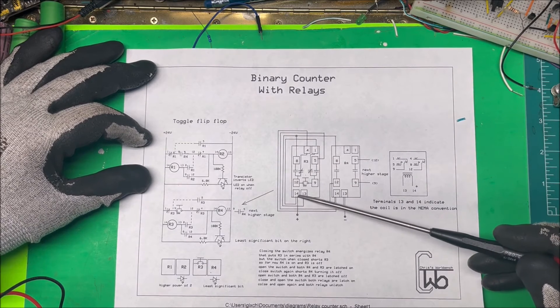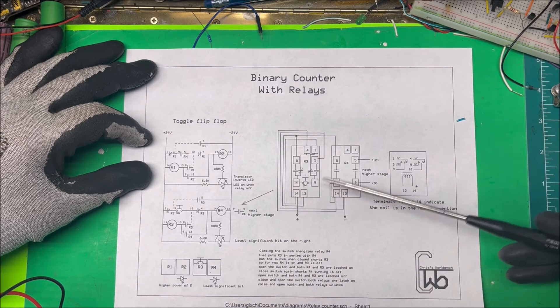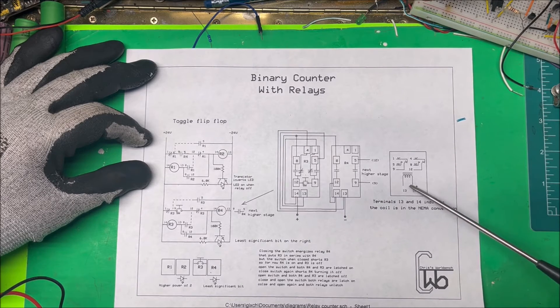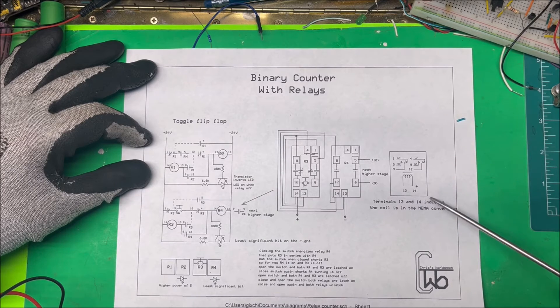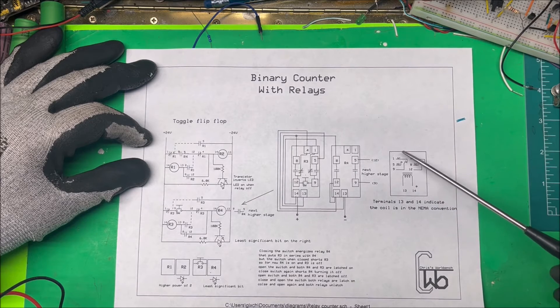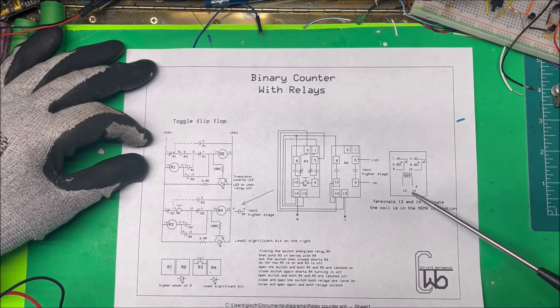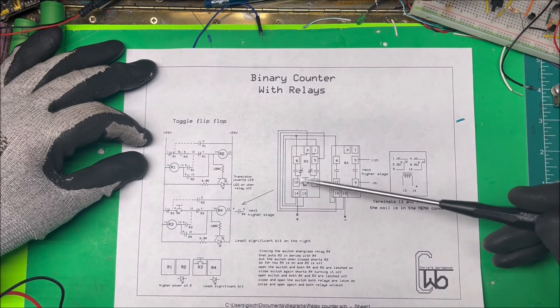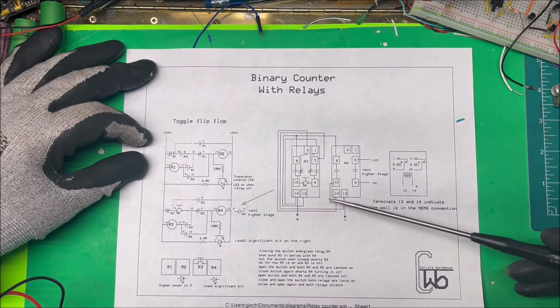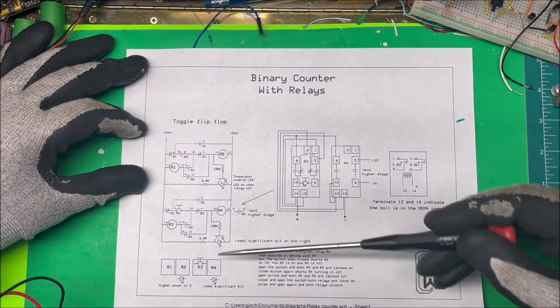That's all there is to that, and then this is how we can wire it together here. Now on these relays, 13 and 14 are the coil. Here it is over here. When you see the 13 and 14, that indicates that it's a NEMA convention coil. They do that so that single pole, double pole, triple, and quadruple pole relays will all work and have the same numbers. Some of the relays come just one through eight and that's fine too.